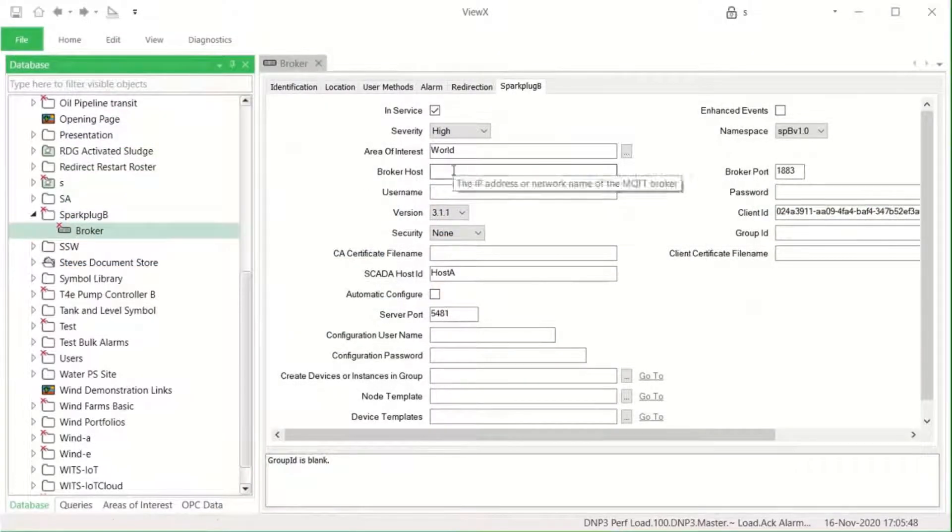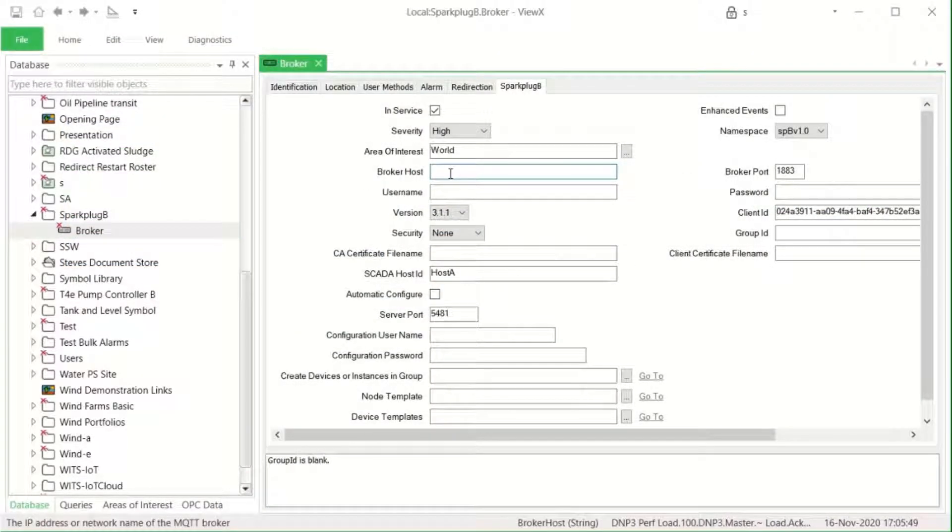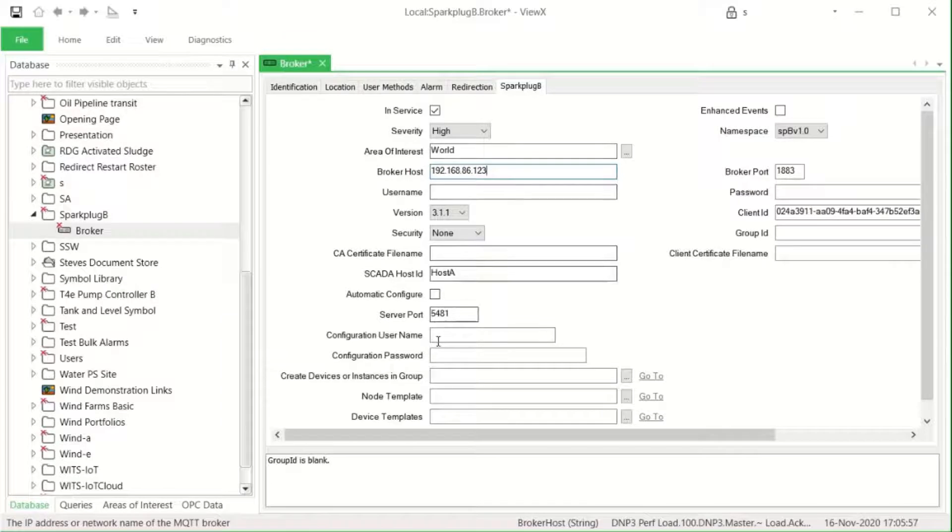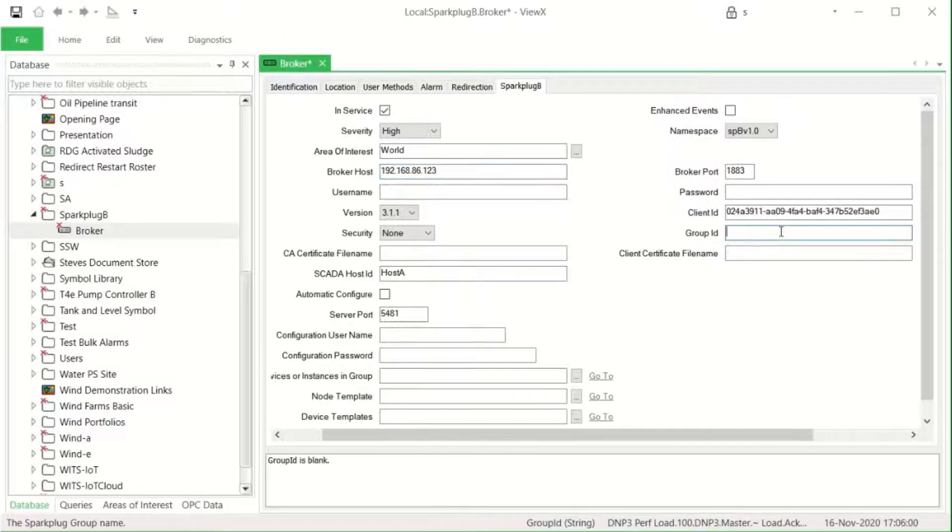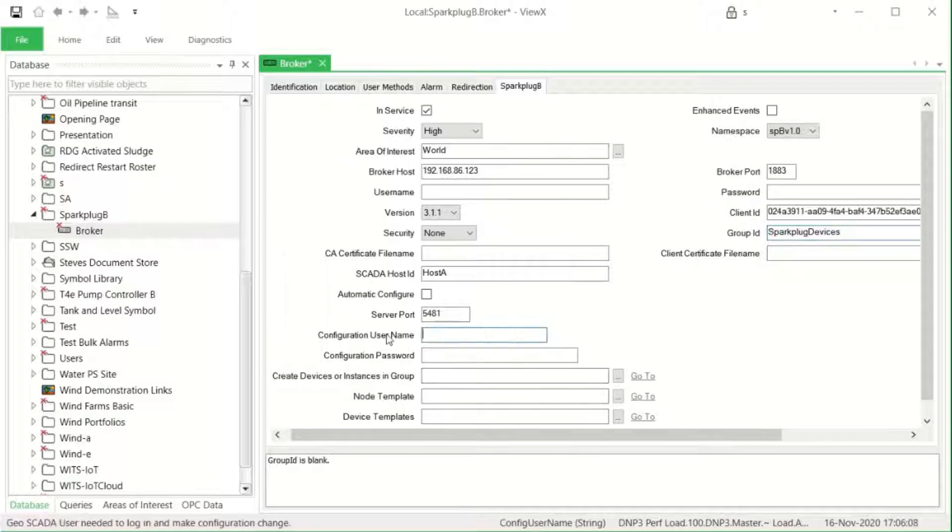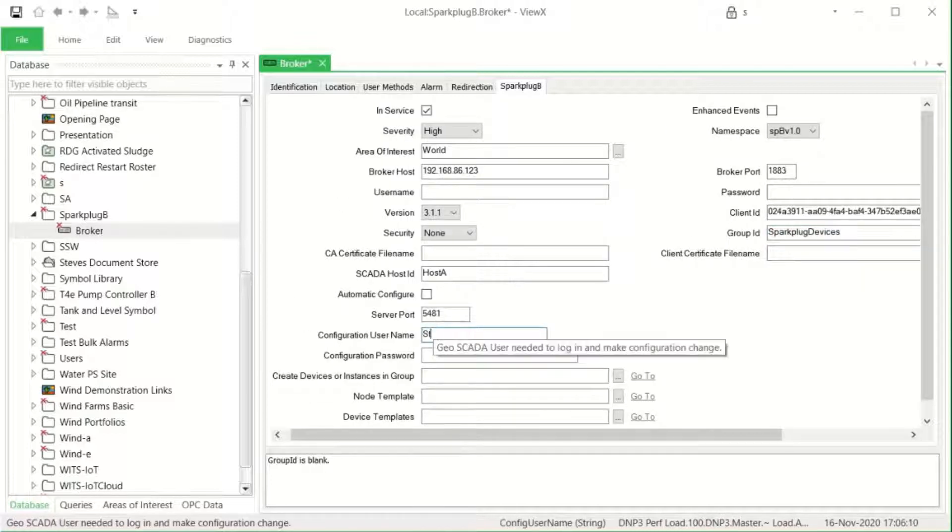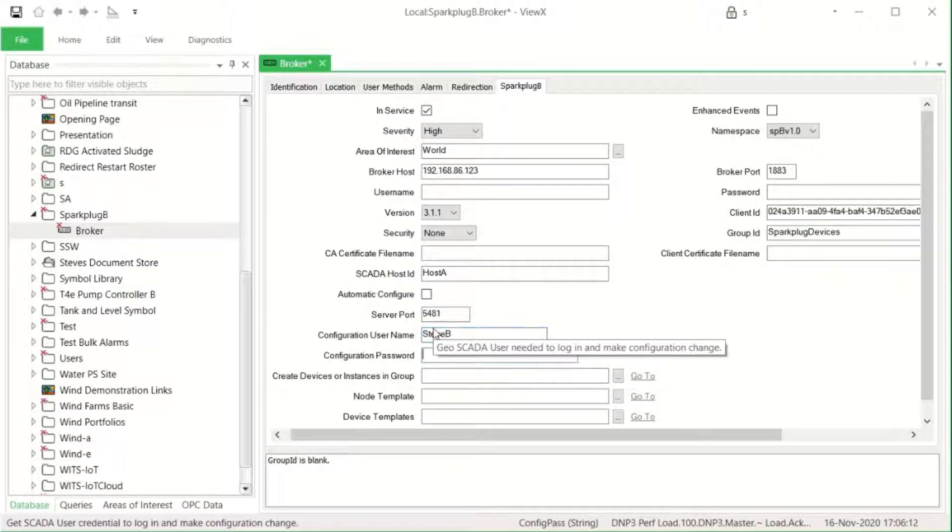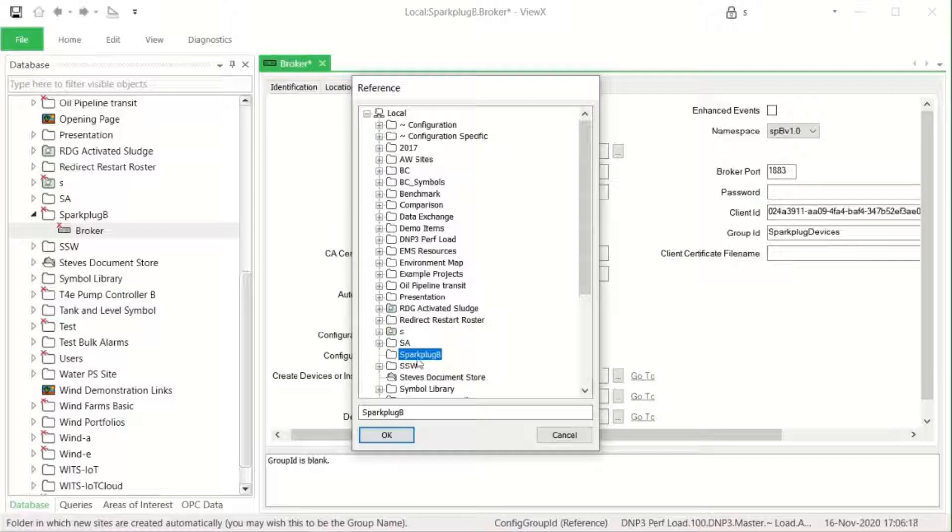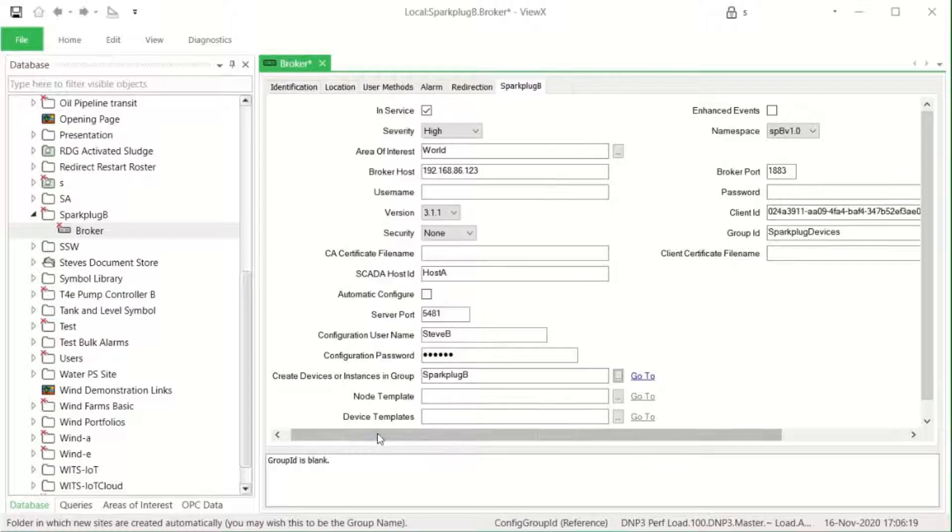We're going to start by creating and configuring a single GeoSCADA object, a broker object. We configure this to point to the broker and specify the server to enable communications. We also place it in service. We configure the group ID which defines the group of devices to which Sparkplug will connect, and we'll configure a username and password with configuration credentials in GeoSCADA and the group folder where devices are going to be set up.